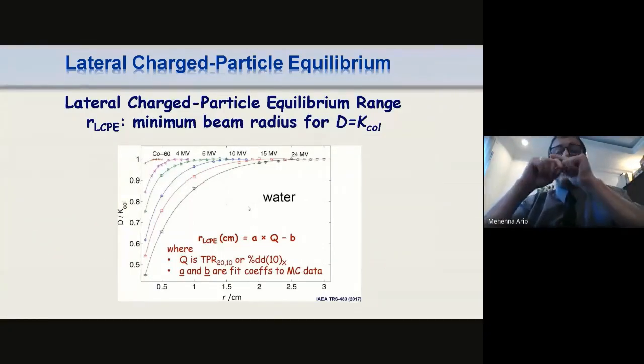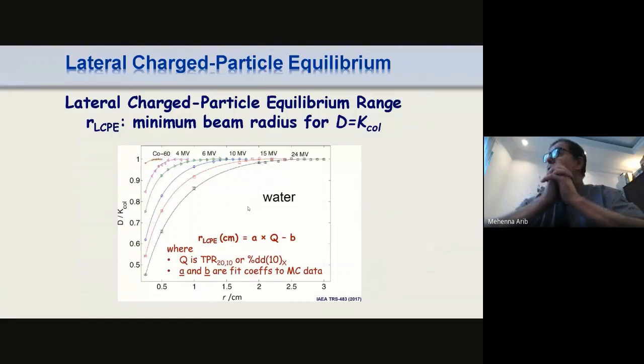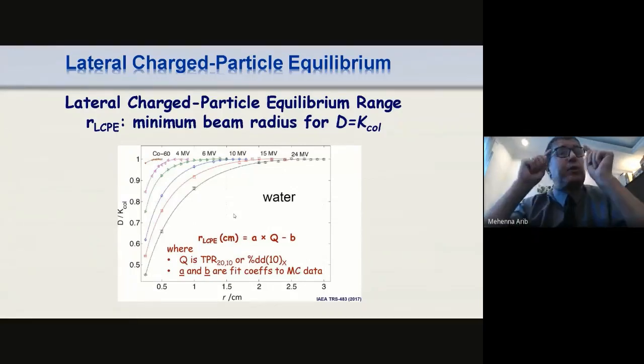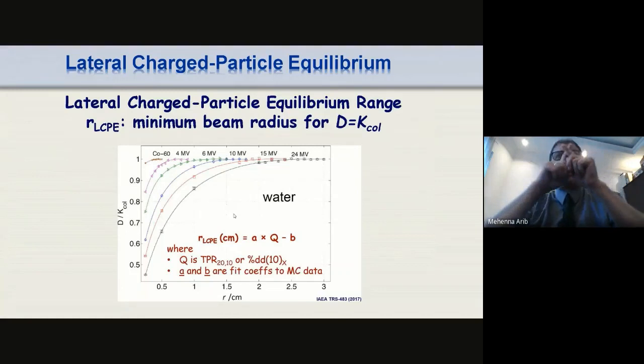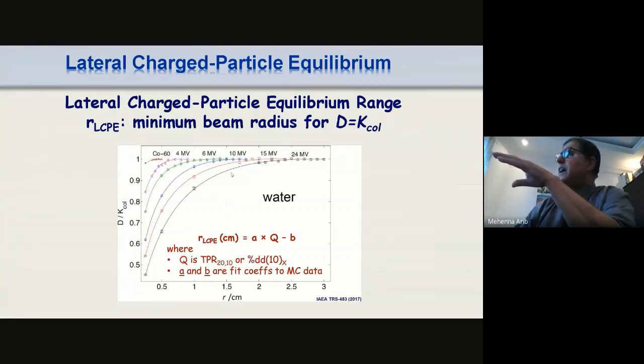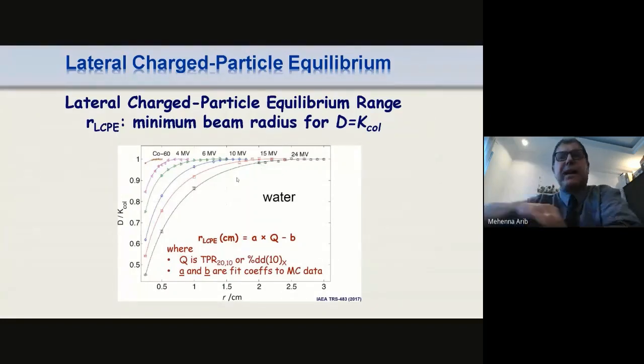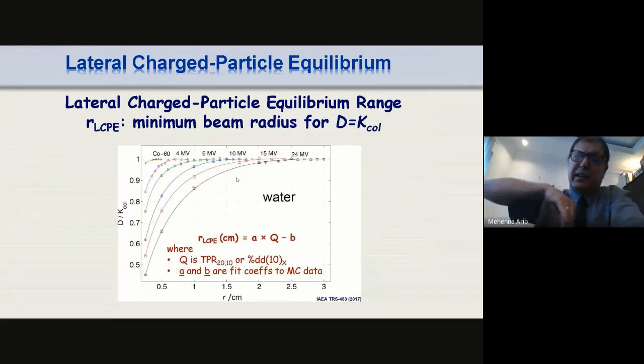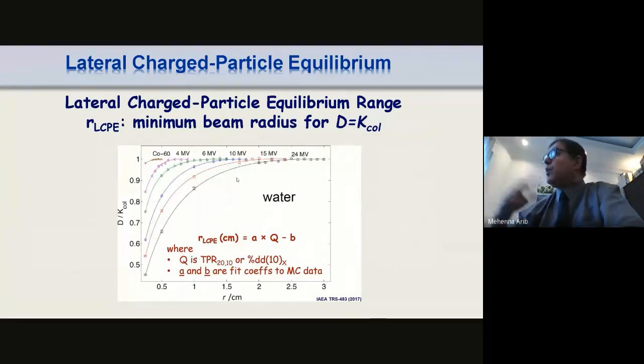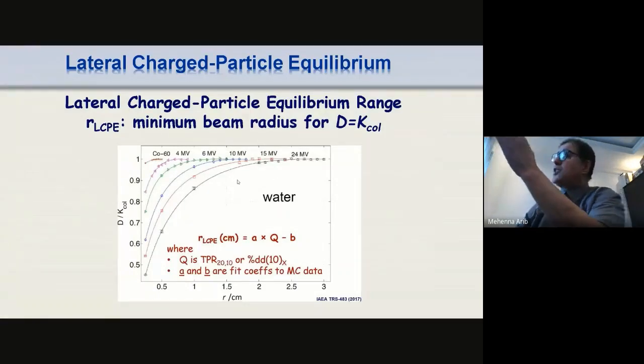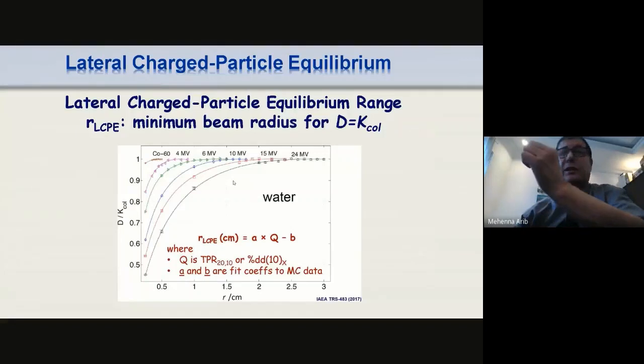Lateral charged equilibrium. Exactly. So now let's go and check which kind of ionization chamber you are going to use for the small fields. A group of researchers tried to calculate the lateral charged particle equilibrium, which is one of the requirements for the application of the code of practice, because the dose to water is equal to the collision kerma when the lateral charged particle equilibrium is realized. You will see that for different energies and different beams, the lateral charged particle equilibrium is not achieved for all the energies. It is achieved for a higher radius of the chamber for higher energy.